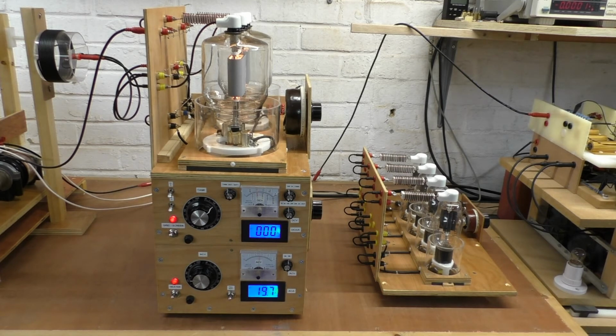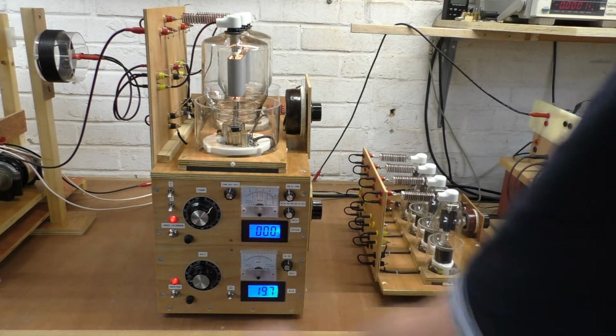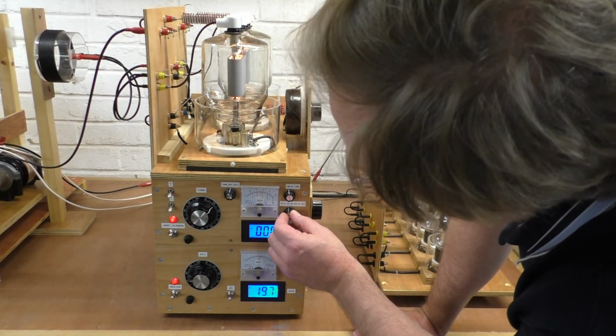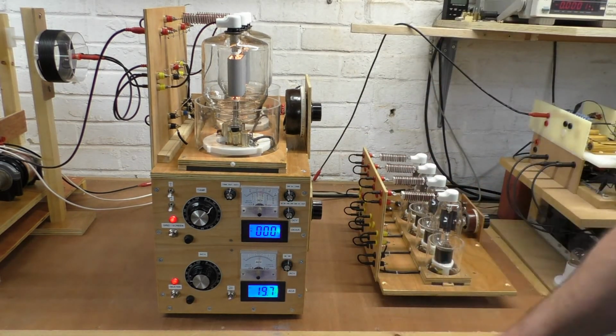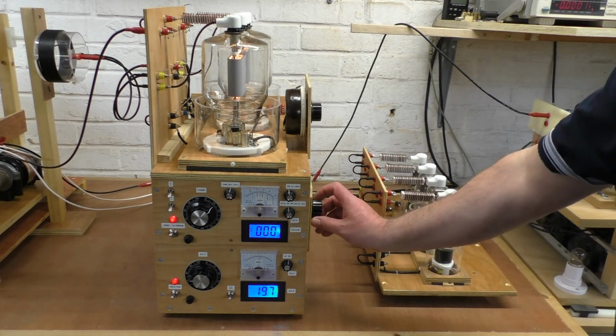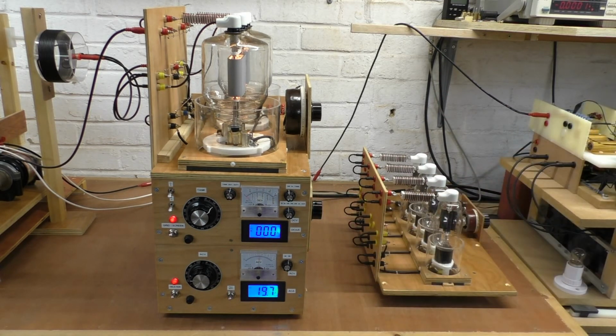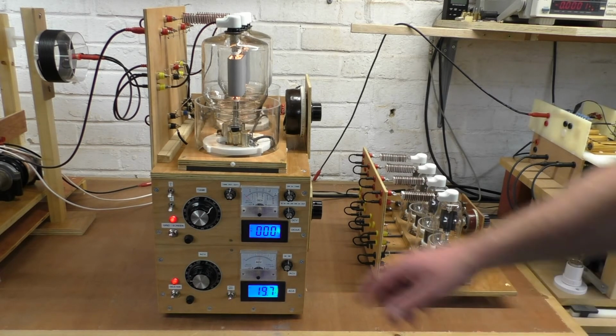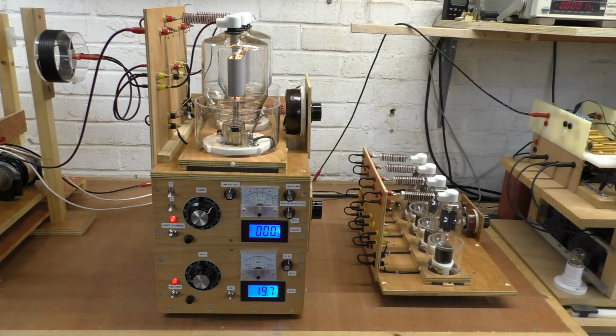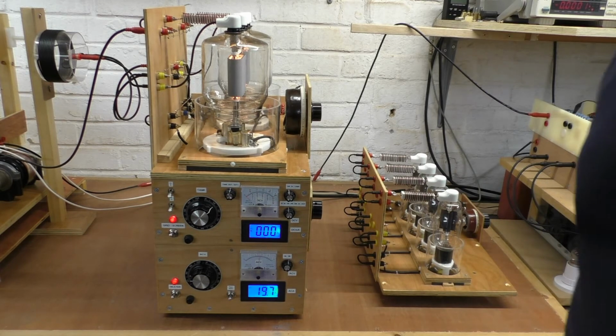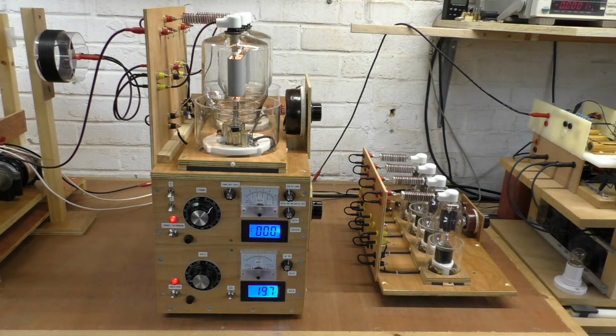The tank is up 200 volts. So if I now switch over to the output, the output is currently on 100 volts full scale deflection, and we're reading 50, a central point. If I go fully up to the high point of adjustment, we're now showing 0 volts. So because we've got our output setting from 0 to minus 700 for full tank, in effect we are now set from 0 to minus 100. That is a range of available biases.